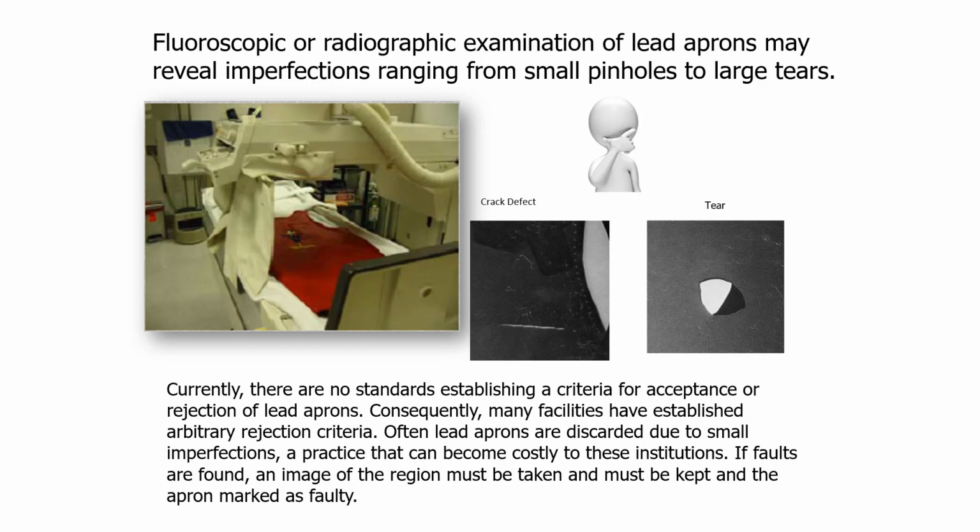Because people have radiophobia and they're scared of radiation, we may throw a perfectly good lead apron away because it has a small crack, defect, or tear. On the other hand, how much efficiency have you actually detracted from that entire barrier with the small crack, deficiency, or tear? That's where subjective knowledge comes in handy on whether we keep it, repair it, or dispose of it.